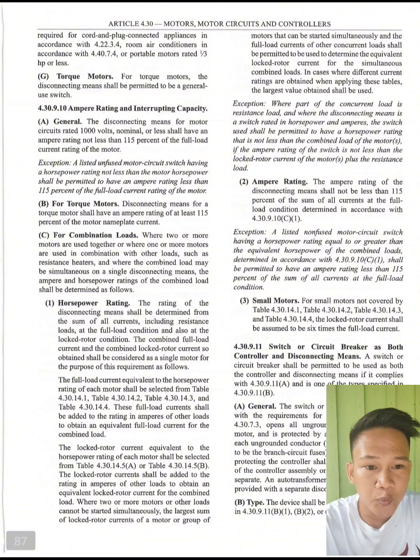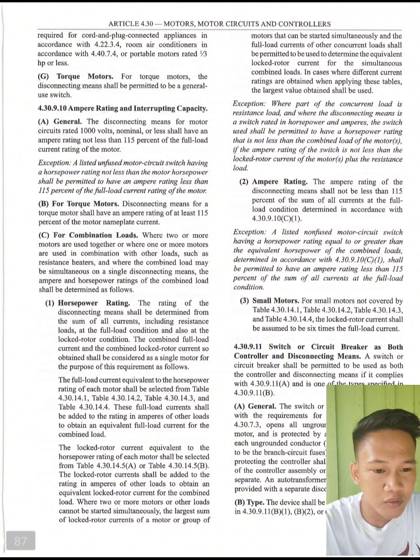Next, we have 4.30.9.11, switch or circuit breaker as both controller and disconnecting means. A switch or circuit breaker shall be permitted to be used as both the controller and disconnecting means if it complies with 4.30.9.11a and is one of the types specified in 4.30.9.11b.